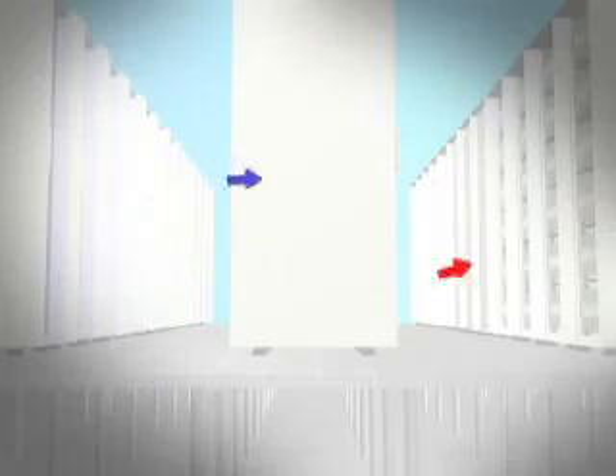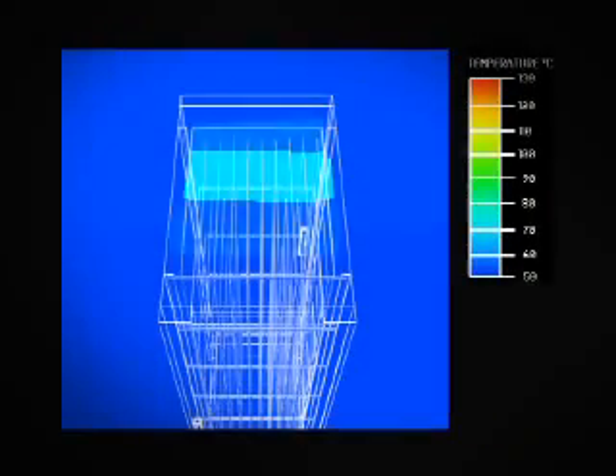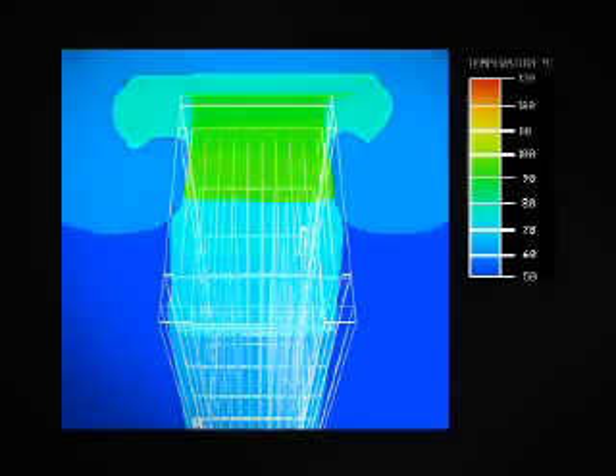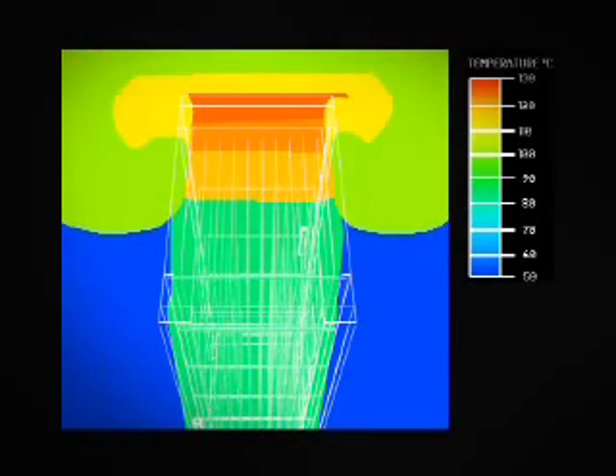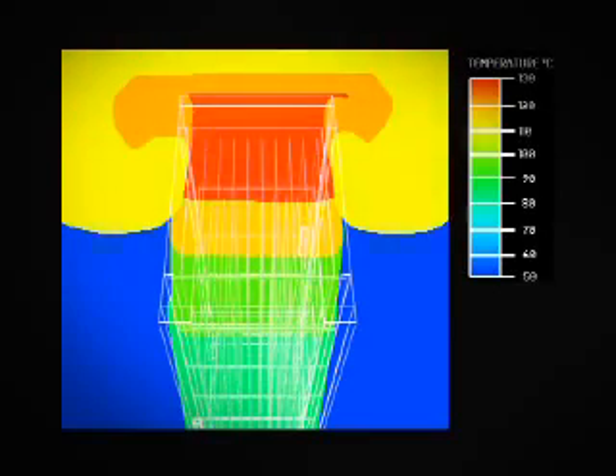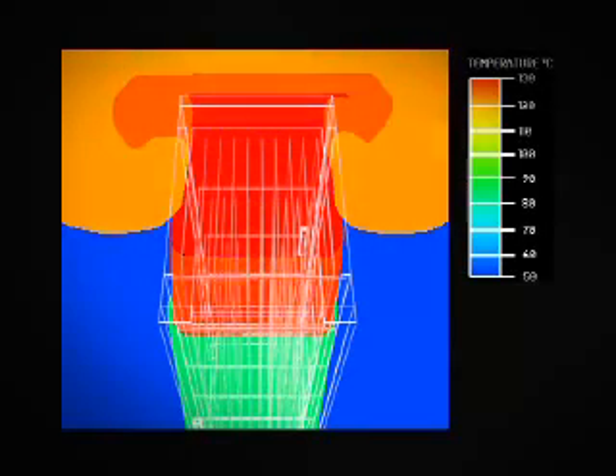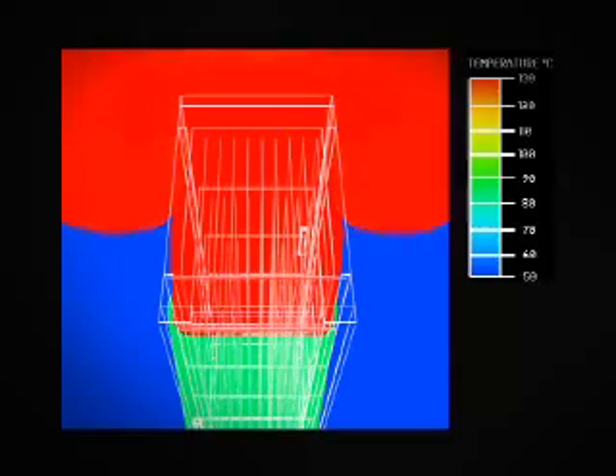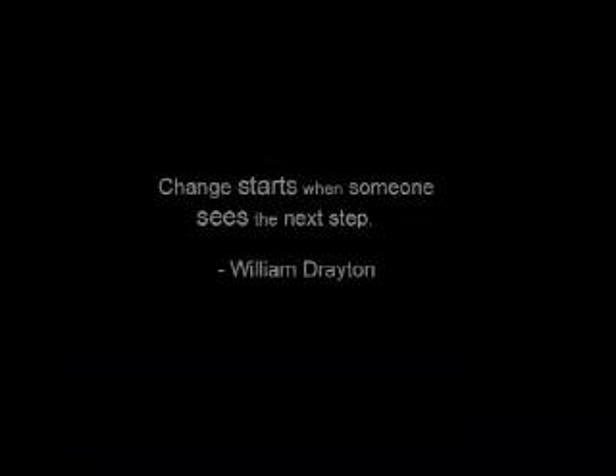More importantly, cooling capacity per cabinet is limited to about 5 kilowatts. Blade servers can no longer be supported using traditional cooling methods. A new thinking now needs to be deployed to ensure that your critical IT network has the right environment to run 24/7, 365 days a year.